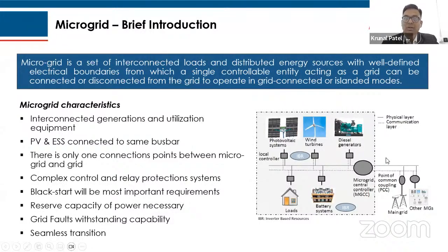the main grid. So it is very important to connect and disconnect, so as to connect to the grid and also work in islanding mode. This is a very important characteristic to be played by the microgrid. Apart from that, looking at the microgrid characteristics in detail, a PV and ESS are required to be connected on the same bus bar. There is only one connection point between the microgrid as an overall grid and the transmission grid.